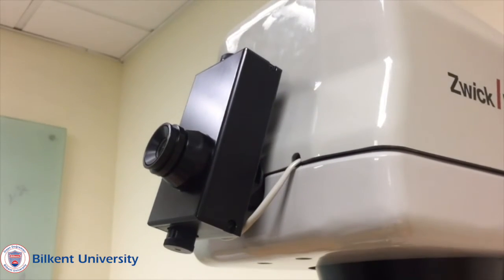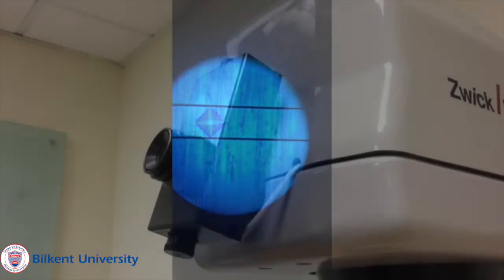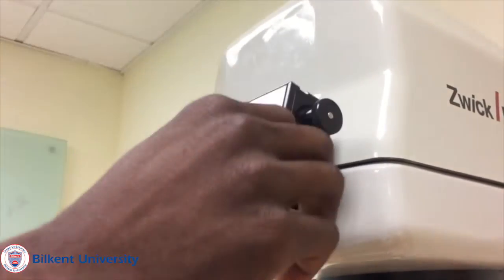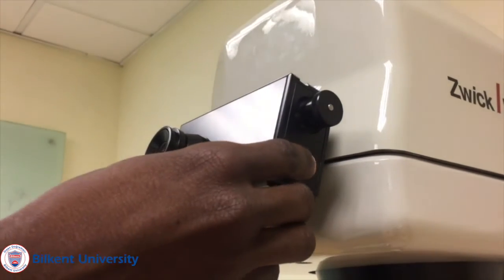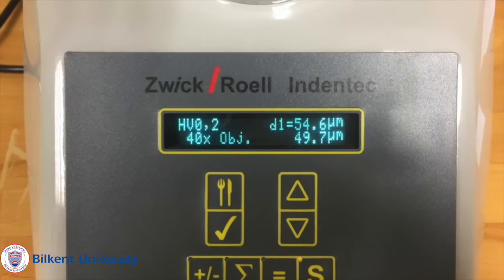To take our measurements, you would need to adjust the left-hand knob whilst looking through the viewfinder, and this would adjust the pair of the parallel lines over the specimen. You will need to set the left line to the left edge of the indentation and adjust the right knob until the right line is aligned to the right edge. When completed, touch the red button to take the readings and flip the viewport through a 90-degree angle, and repeat the same process, this time starting from the bottom line and using the top knob to align the top line. When this is done, you could bring back the viewfinder to its original position and press the red button to collect the dimension and the hardness value.